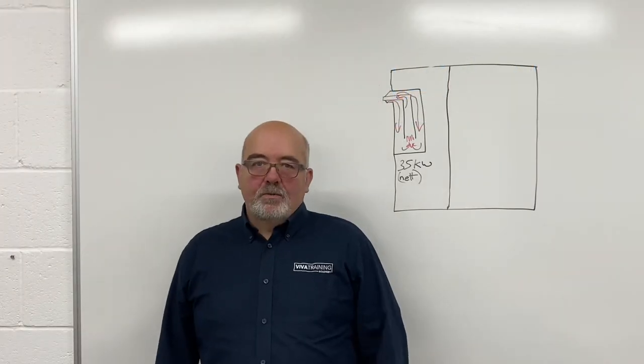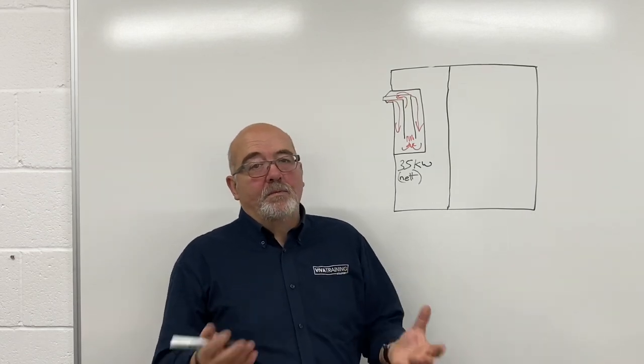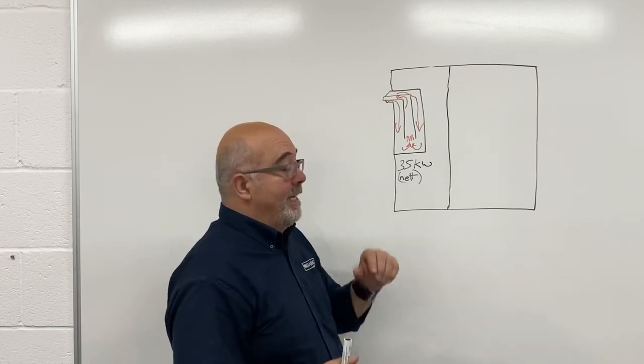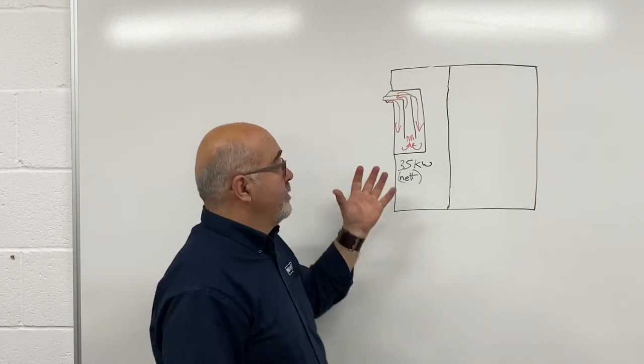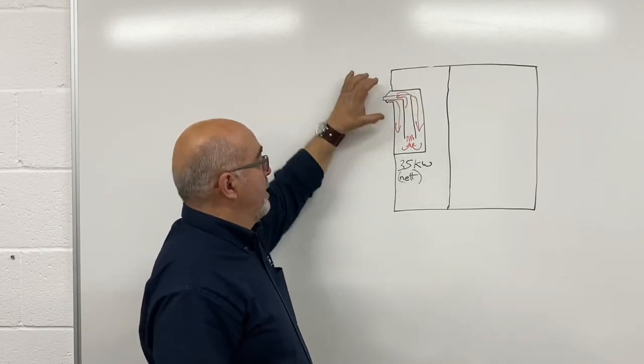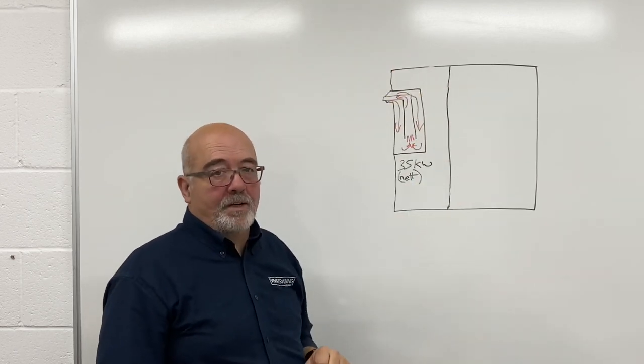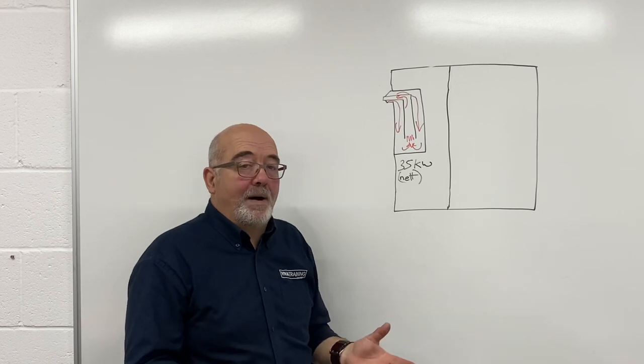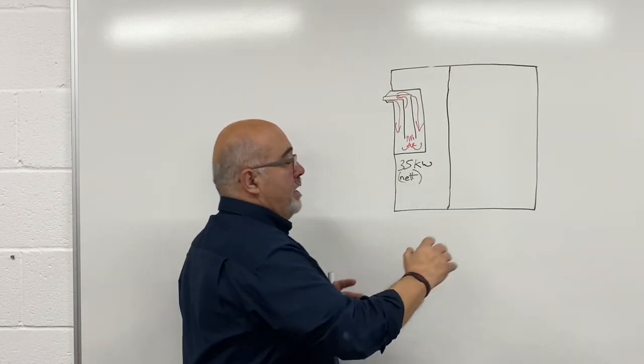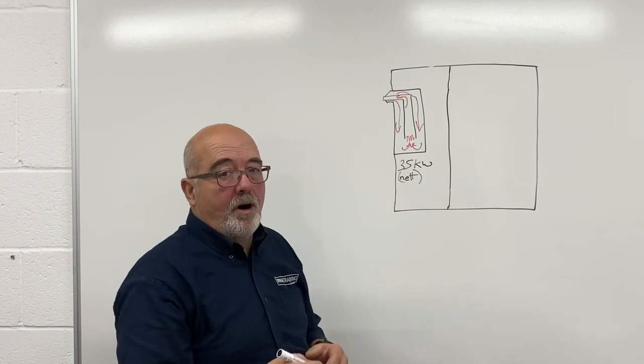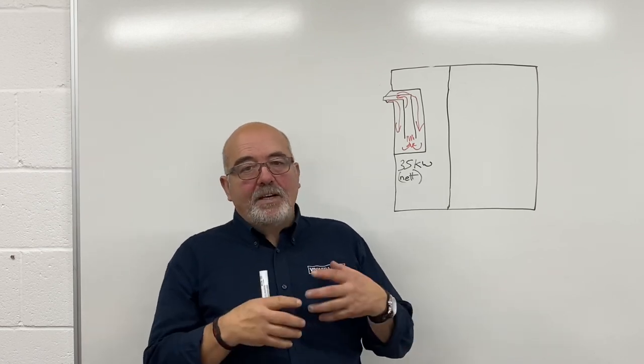Room sealed appliance ventilation: as you should already be aware, the difference between a room sealed appliance and an open-flued appliance is that it takes its combustion air from outside directly into the appliance. Here I've shown a relatively modern setup with a fan-assisted flue bringing combustion products out and combustion air in. So all we're concerned about is cooling air in the actual compartment. If it's in a room without a compartment, it wouldn't be a problem — but if it has a compartment, check the manufacturer's instructions.